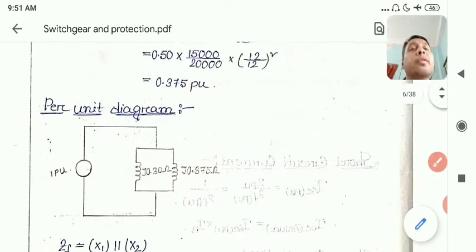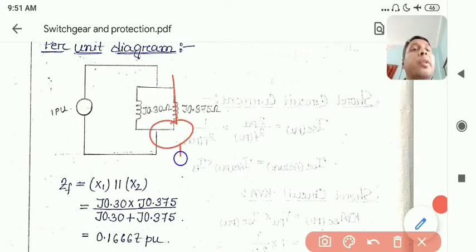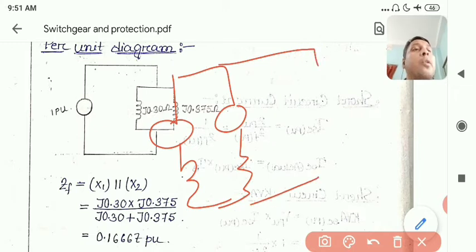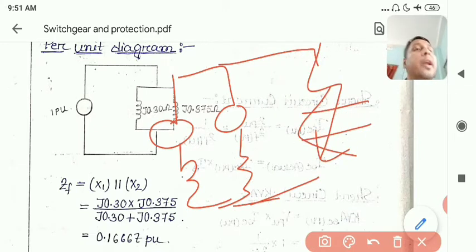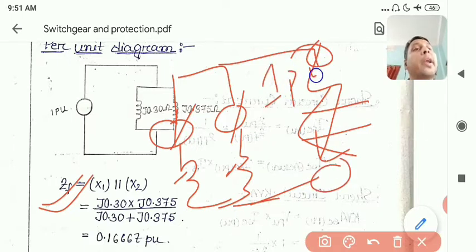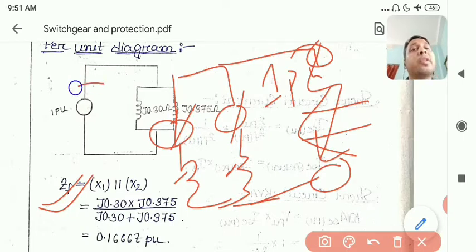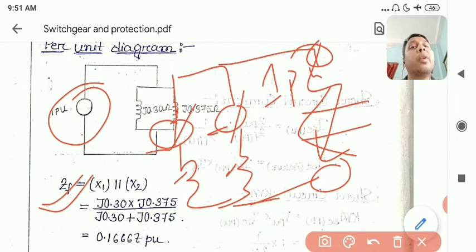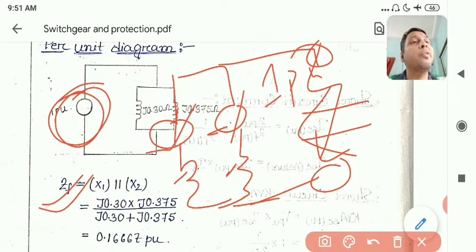Drawing the network: the fault is occurring at a node. Looking from the fault point, we calculate Z_f using Thevenin's theorem. The Thevenin voltage is the pre-fault voltage, which is always 1 per unit at any point in the power system. The Thevenin impedance Z_f is obtained by killing the voltage sources (short-circuiting them), leaving the two reactances in parallel combination.